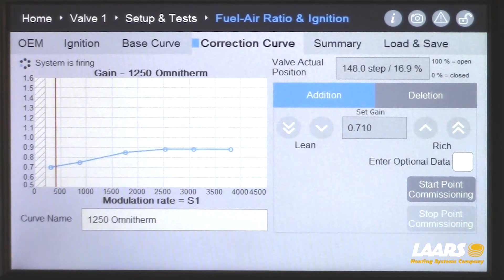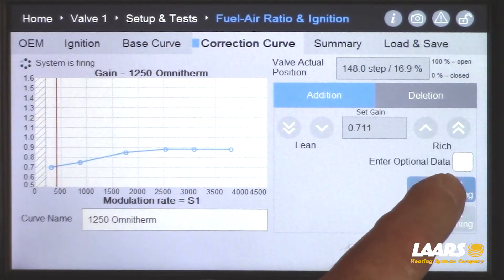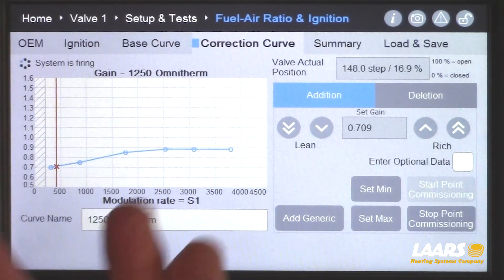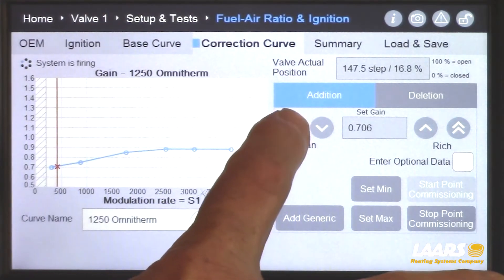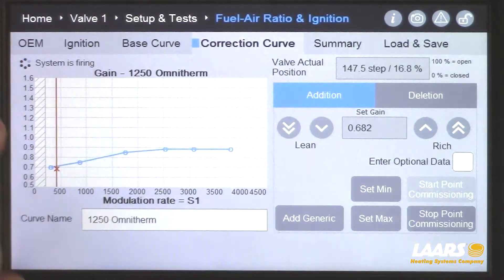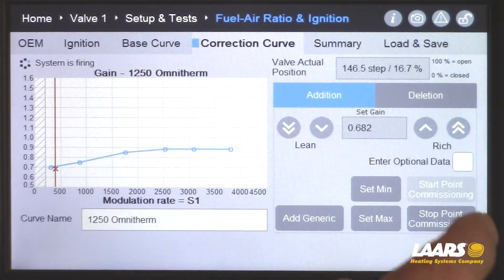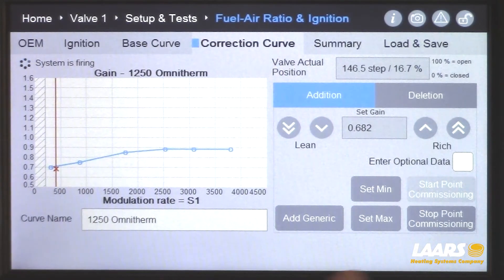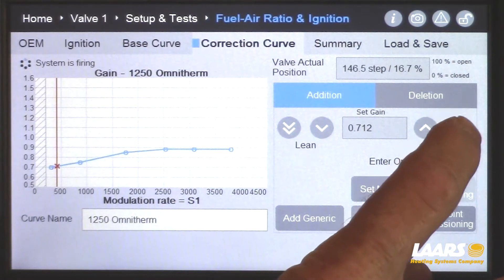Let's say you were running higher or lower and had to make a change. On the red air line, click start point commissioning and an X will appear. If you need to decrease or lean it out, simply drop your value and you'll see the X drop down on the air indicator line. In this example I'm going to bring it back up because I was right on, and I'll click save. Any time you click start point commissioning, that X will appear and you will have to save it. Bringing it back gives me 8.5%.